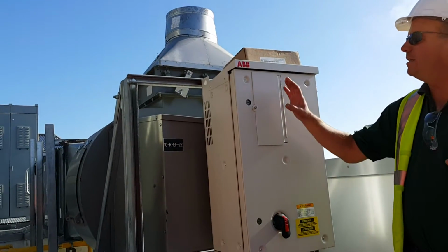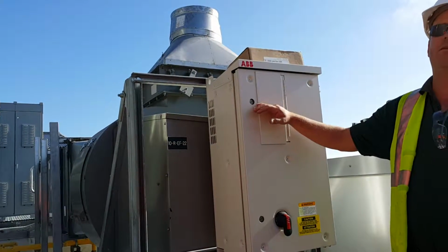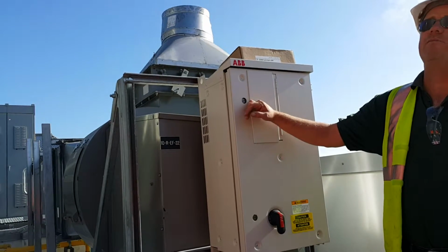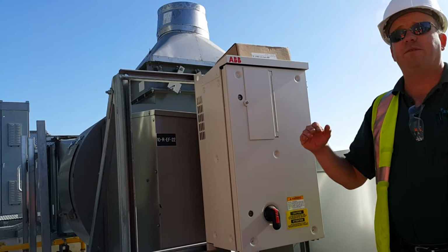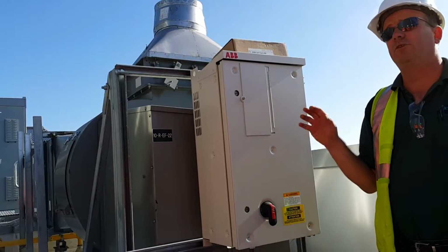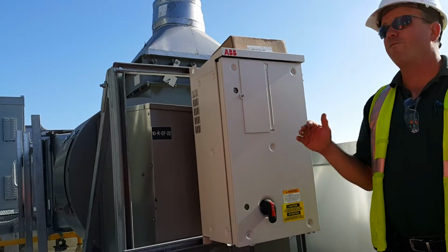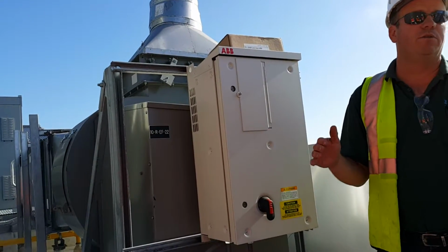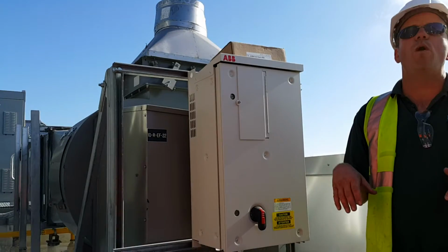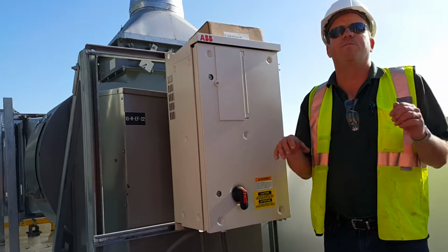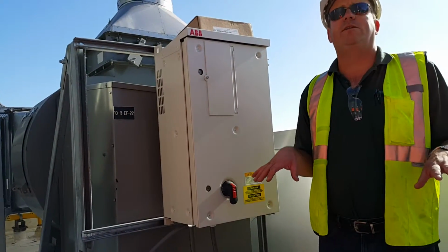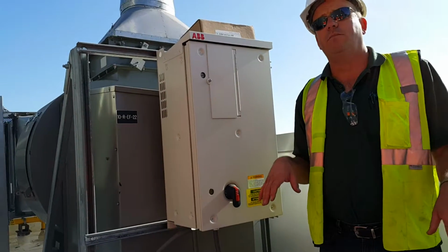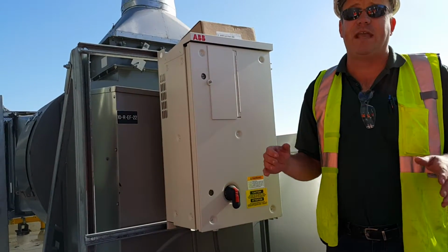So if you see the drive, like I say, if you don't see a fault on there, don't worry about it. If you see an alarm, so there's two different things. There's fault, there'll be a red light. An alarm is green and flashing. Don't freak out on the word alarm. I wish they wouldn't use the word alarm. Yeah, it's kind of like backwards, right? Well, not really. A fault is the difference between a fault and alarm. Alarm will not shut down the drive. It's not a serious problem. But it should just be called notification.